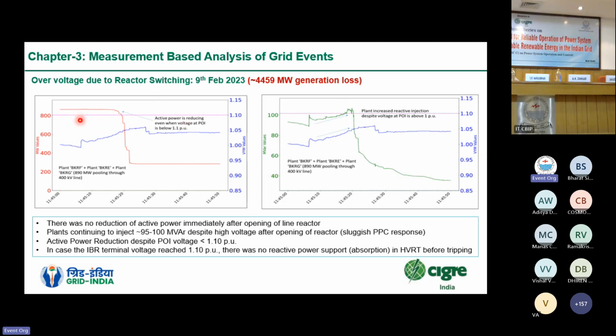This is the active power of a typical plant during that period. At this instant, the reactor was opened. Voltage was nowhere near the HVRT limits. The active power also did not reduce at this point of time. But then we can see this gradual rise in voltage. This can be explained through this plot where the reactive power of the same plant is also plotted. Even when the voltage is increasing, there is no reactive power support from the RE plant.